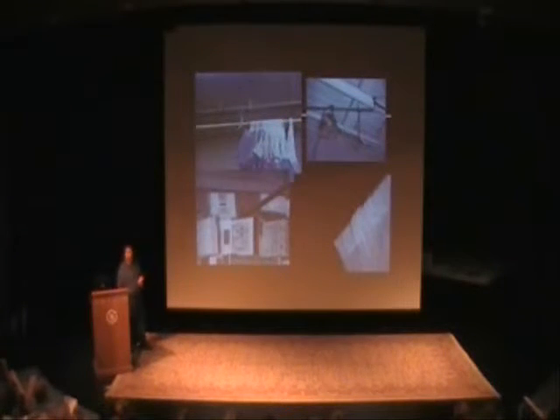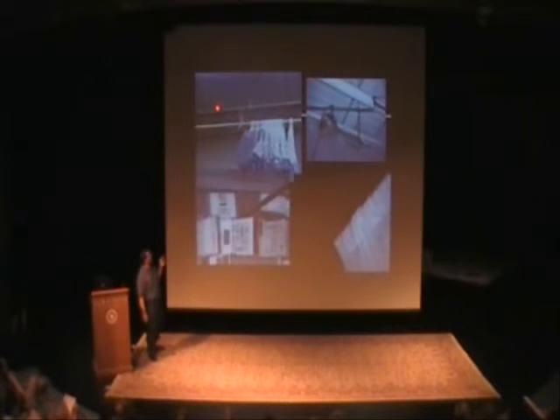Obviously, someone needed some more hanging space. The only thing that can hang from a sprinkler pipe is a sprinkler head, period. No questions asked. No phone wires, no data wires, no nothing but sprinkler heads. No wires. You can't even loop them across.